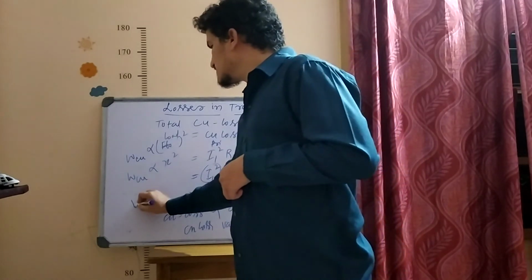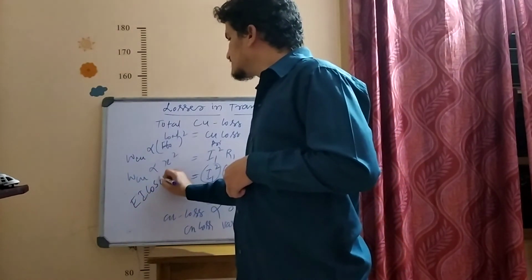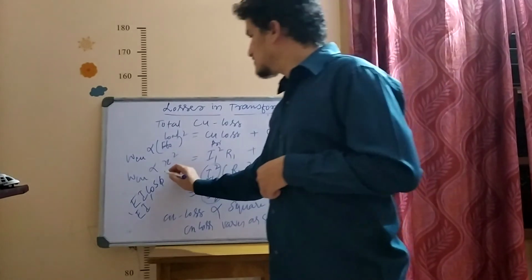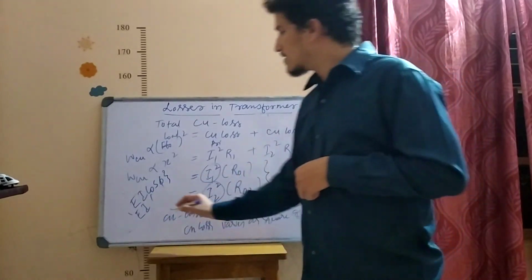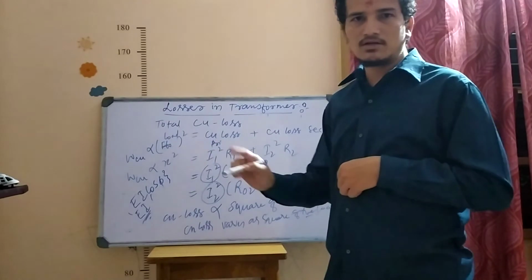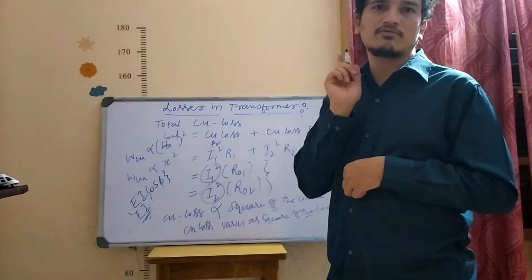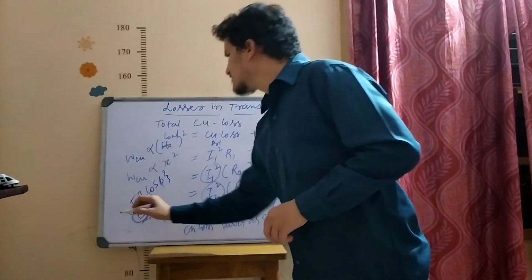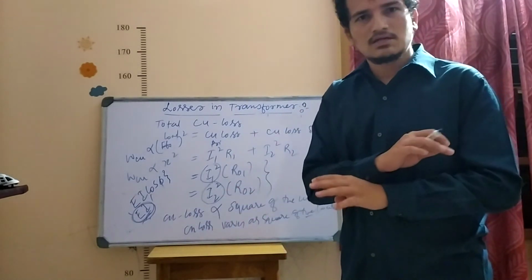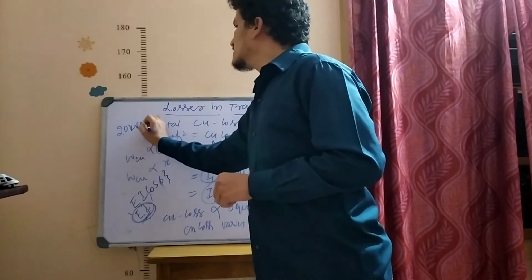So you cannot express that in EI cos phi. In general, you will represent the rating by EI only. You don't know the type of load connected. The overall power that it can deliver, maximum, is at unity power factor. Above this, you cannot rate the transformer. Say for example 20 kVA is the maximum power.